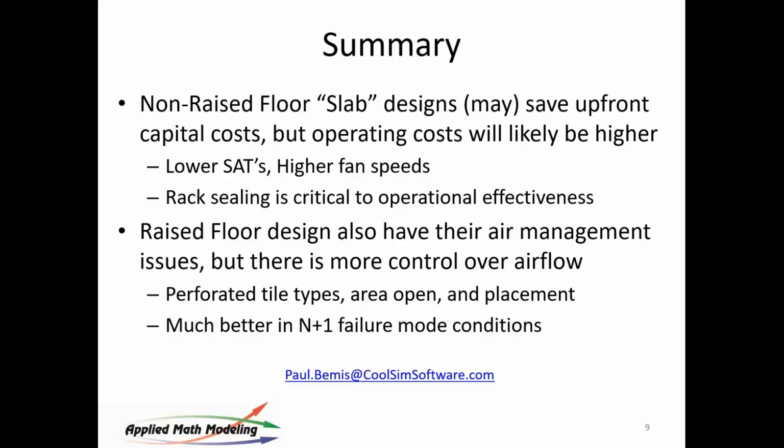And one of the things I'm a little bit concerned about here is that the elimination of the raised floor data center as a design of choice is a capital expenditure issue. Fundamentally, the cost of putting the raised floor design in place can be avoided using some of these fan wall designs or some of these flood the room air designs, slab designs. However, they are not thinking about the operational cost.